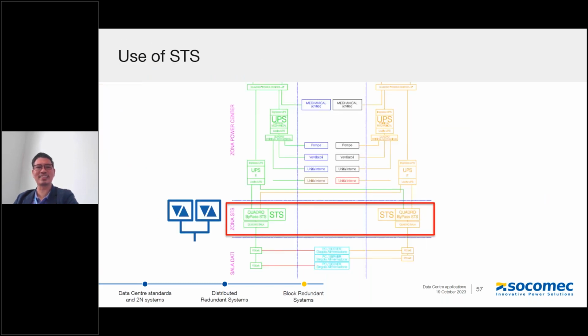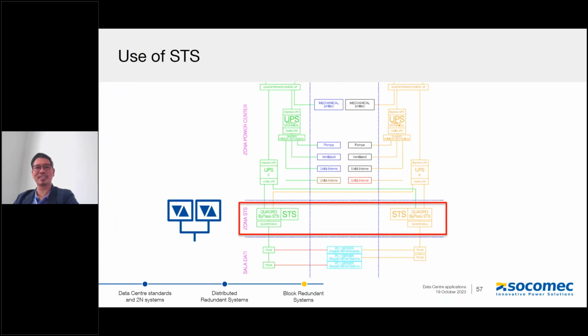As you can see here, these are the common issues, and that's where an STS can bring benefits into the architecture, because it puts the reliability upstream at a higher level, at the PDU level, where the server doesn't have to worry, since they will still maintain the redundancy they need.